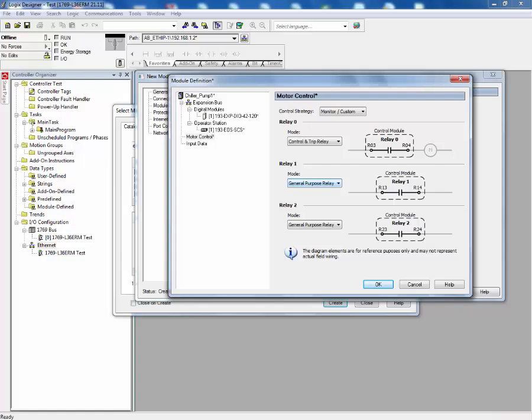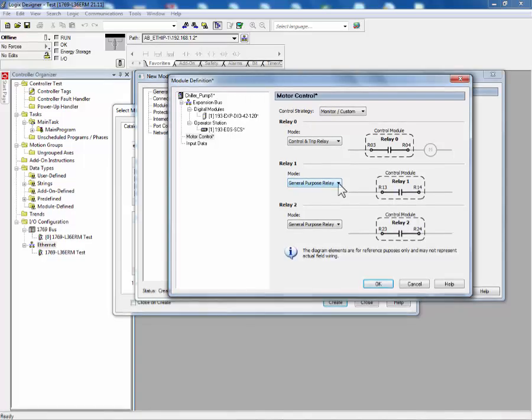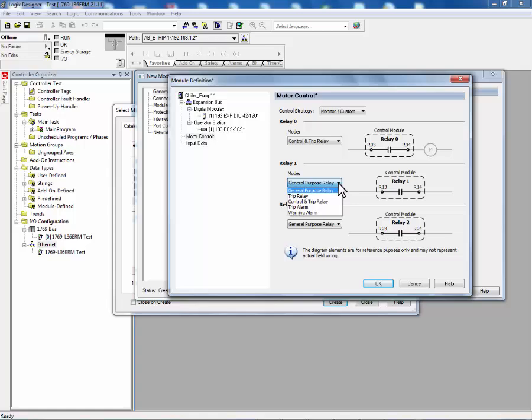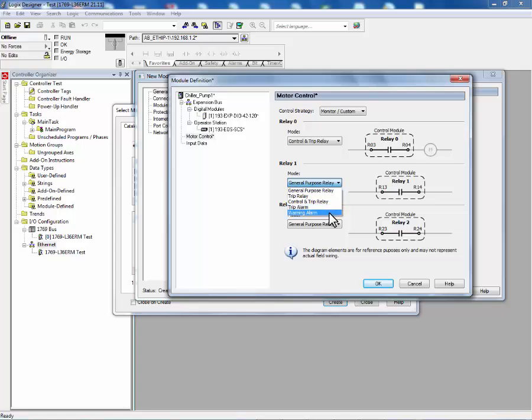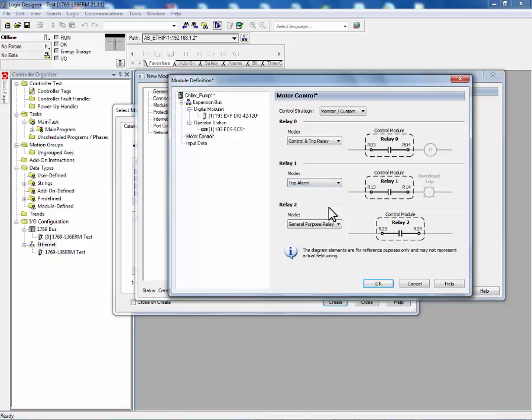Other selections that are available are a trip relay, a trip alarm, and a warning alarm. In this example, we will configure relay 1 to be a trip alarm. The trip alarm is a normally open contact. In the event of a trip condition, this relay will close. This can be used to illuminate a pilot light to indicate that there was a trip.